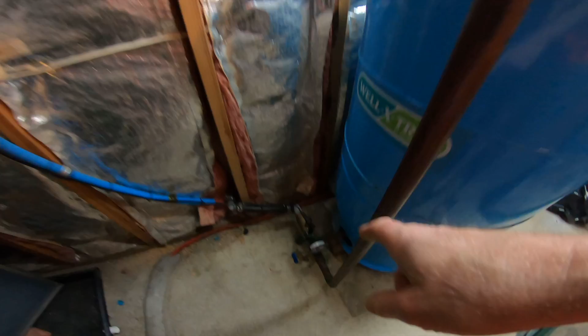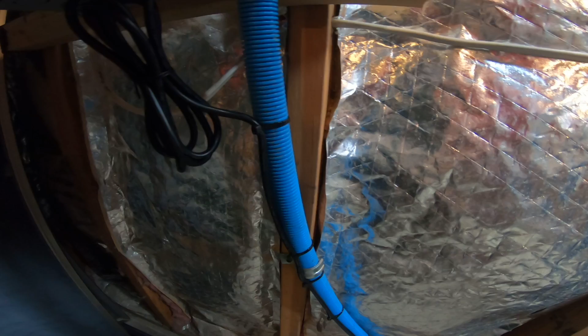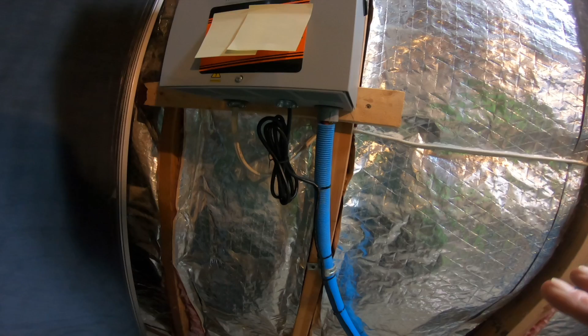We just got this Pentair system. They put this transducer in the wrong place. This wire should not be parallel to this 240 volt wire. If it has to cross it, it's supposed to be at 90 degrees. Not quite the proper installation. It said the wires shouldn't cross each other.